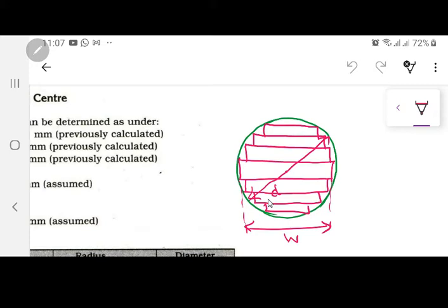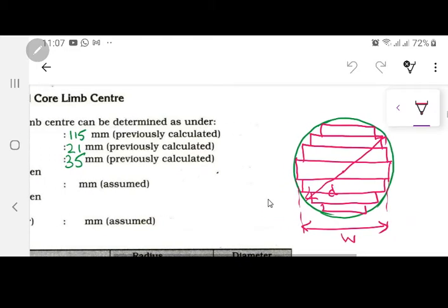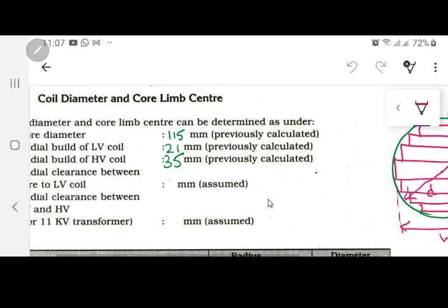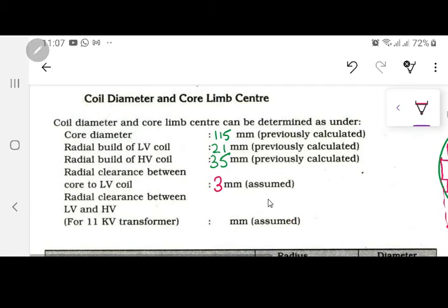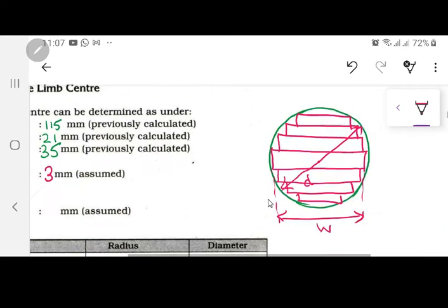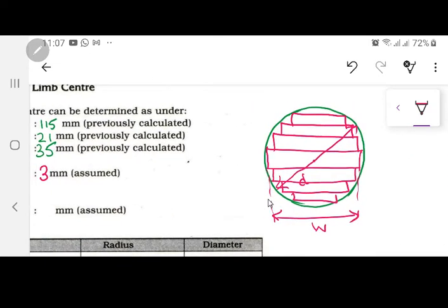That cylinder has to be some material which is not a good conductor of magnetic field. So it can be some asbestos or some plastic or something like that, and that has to be very small thickness, because if you attach something with a thickness of like maybe 10 mm or 20 mm, you are actually increasing the leakage flux again. So according to your book over here, they have taken this data as 3 mm over there. So this is actually the thickness of this green color cylinder on which the windings are going to be done. So this is actually the 3 mm thickness of that.